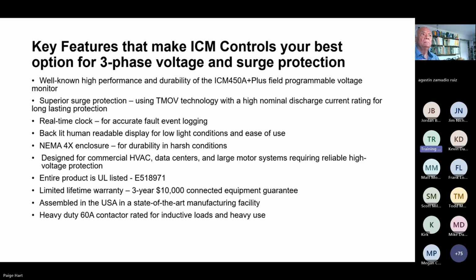The three-phase models, as well as all of our models, carry really good quality TMOV technology, meaning thermally protected metal oxide varistor technology. That's the little surge piece that does the work of suppressing the surges. The key feature about our products is they're UL listed with a very high nominal discharge current of 20 kA, which is the highest that UL will test to.